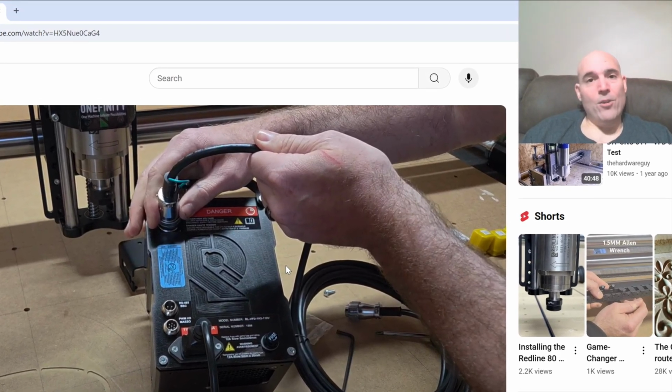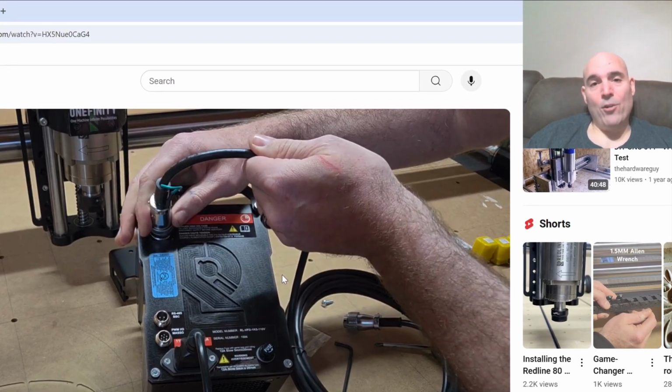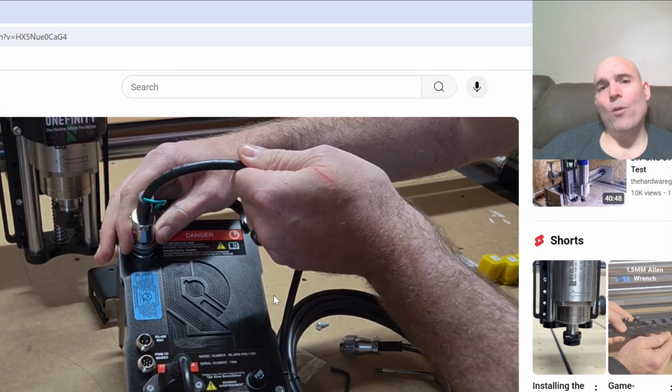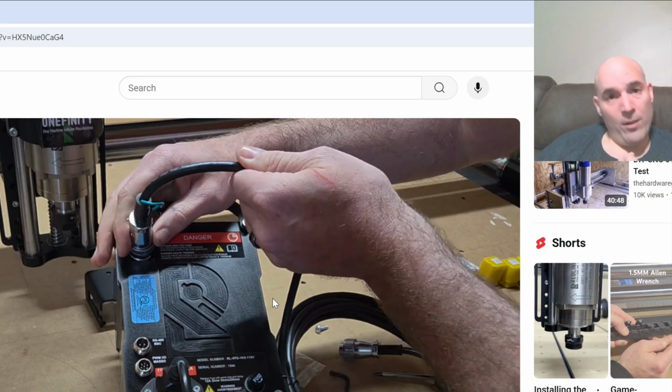Now, I've been told many times that you can do this, and that's of course correct. You can do it, pending, of course, that the metal housing is conductive. Number one, it has no coatings on it. The ohms rating is correct, meaning three or under, because grounding in robotics should be relative to an ohms resistance rating of three or under.